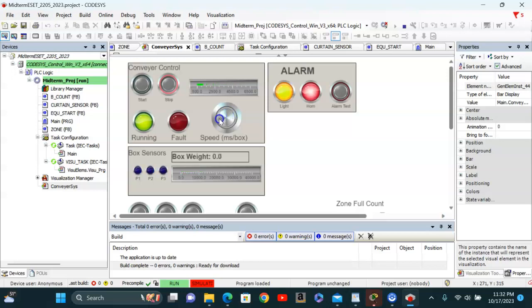Just like that, as soon as we moved it just barely, it should kill off. And okay, there we go. The light was on for 5 seconds and it was off for 1 second. All that was going for 5 seconds and the power was completely killed. Lights were off. Conveyor stops.